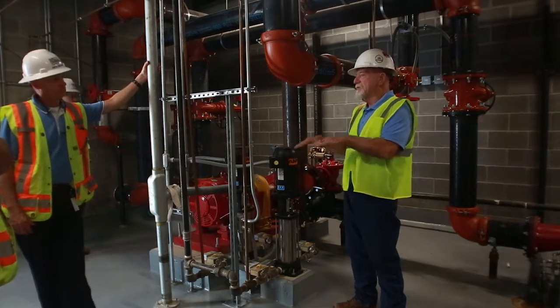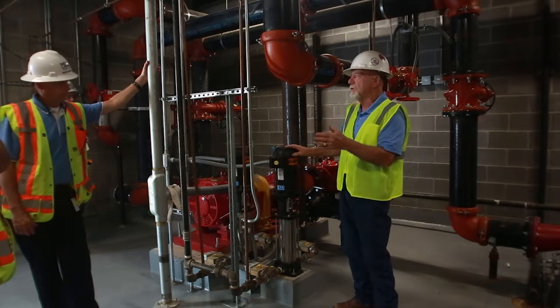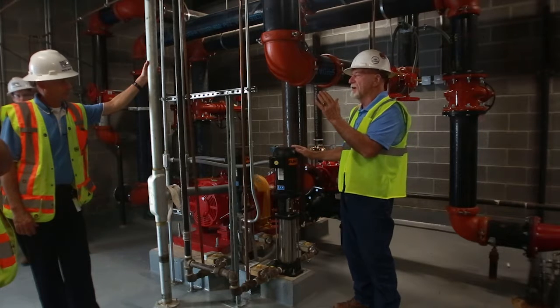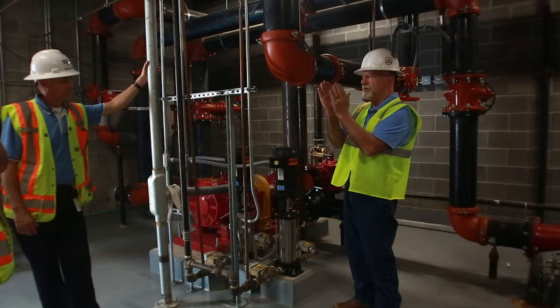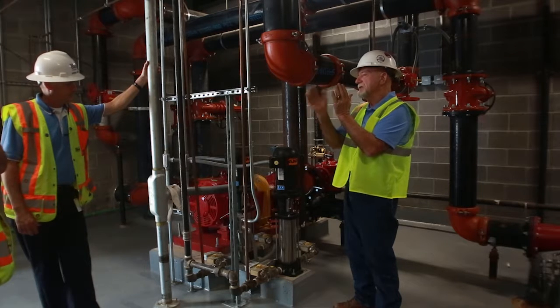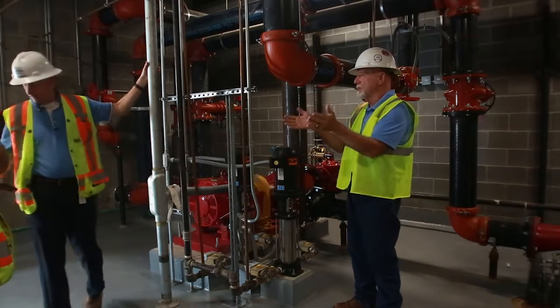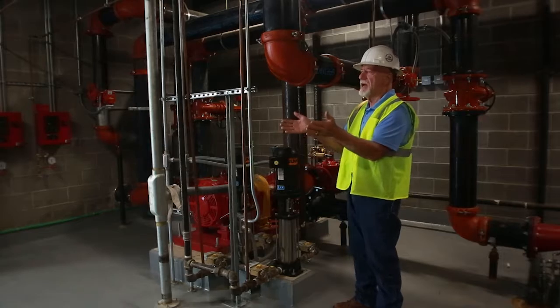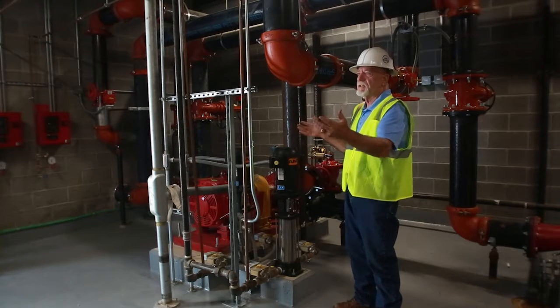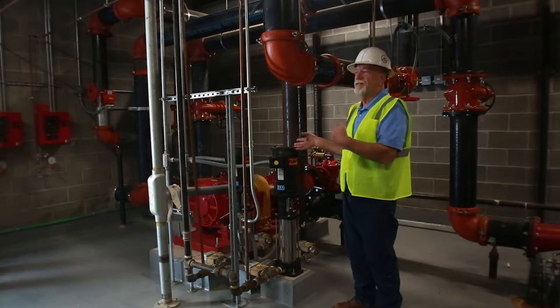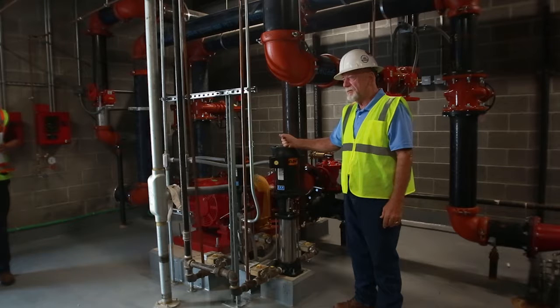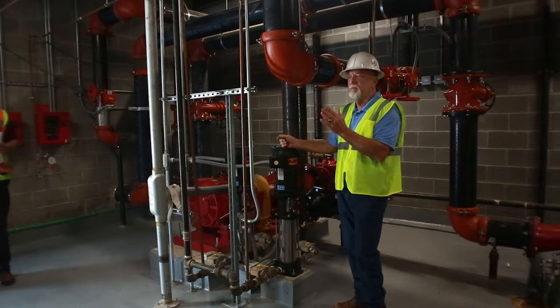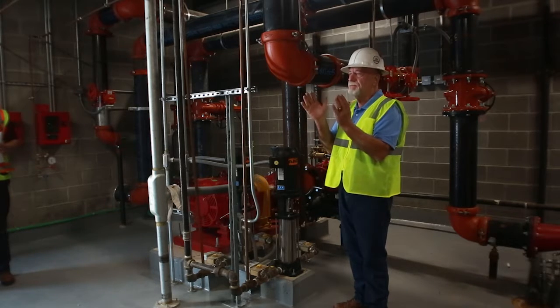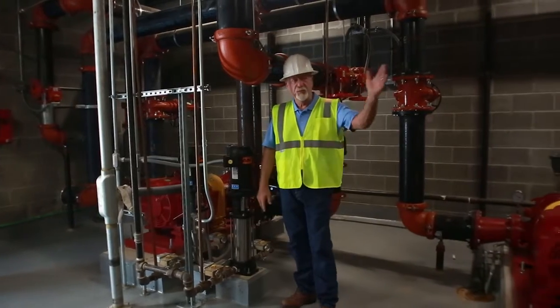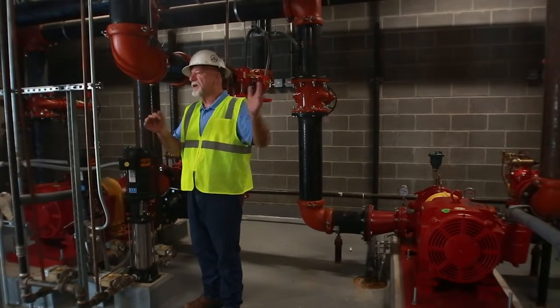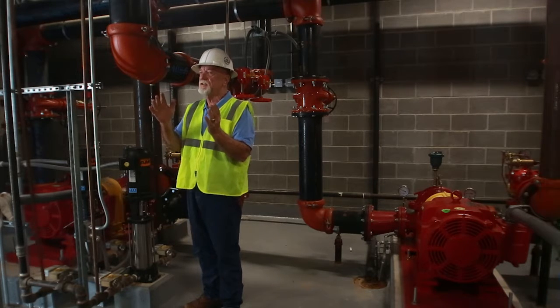Okay. So we raise the values of, if this is cutting off at 150, 152 or whatever, well, as time bleeds over, it may not come on until 125. So you're going to see that 125 to 151 or whatever it is spread. So it's not bad that you can identify that when you walk into the room, because nobody knows these pumps better than you guys do because you see them all the time. And that's kind of where you need to be with this one, just like the others. You need to know what its little caveats are. Right. But presumably you'll be able to put this one up to where you can have that guaranteed pressure, depending on whatever that window is. And then if we increase the pressures on this one, then we increase the pressures on that one. And when I say increase pressures, we're speaking of on and off pressures only. It has nothing to do with generated pressure.